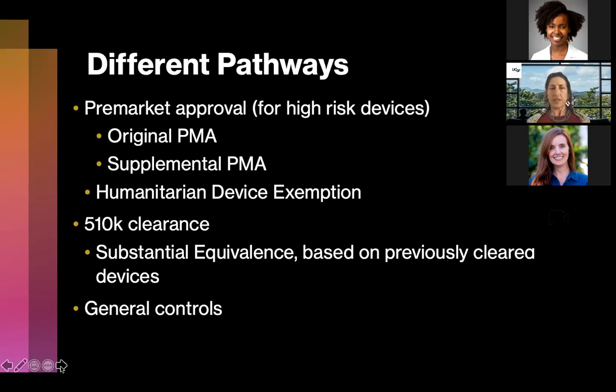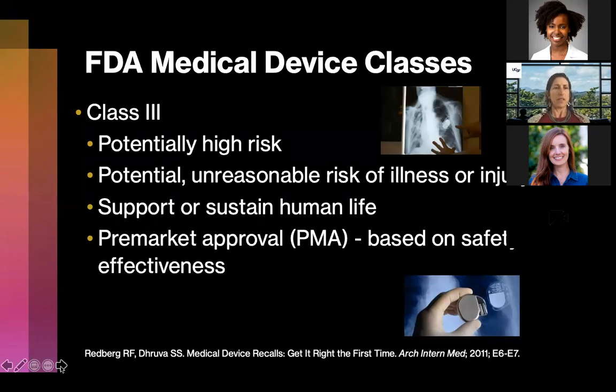So next slide, I'll talk about FDA medical device classes. I'm going to spend a little time on Class Three, because that is what most cardiovascular devices will fall into, or we think so. Although I should note that less than 1% of all devices actually go through pre-market approval, so this is not that common a pathway. It is intended for devices that support or sustain human life, and the criteria for approval in this pathway is safety and effectiveness.